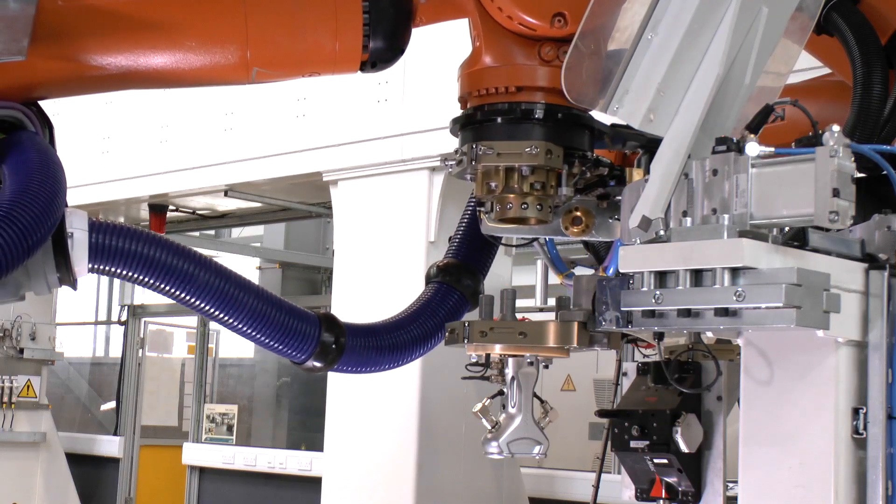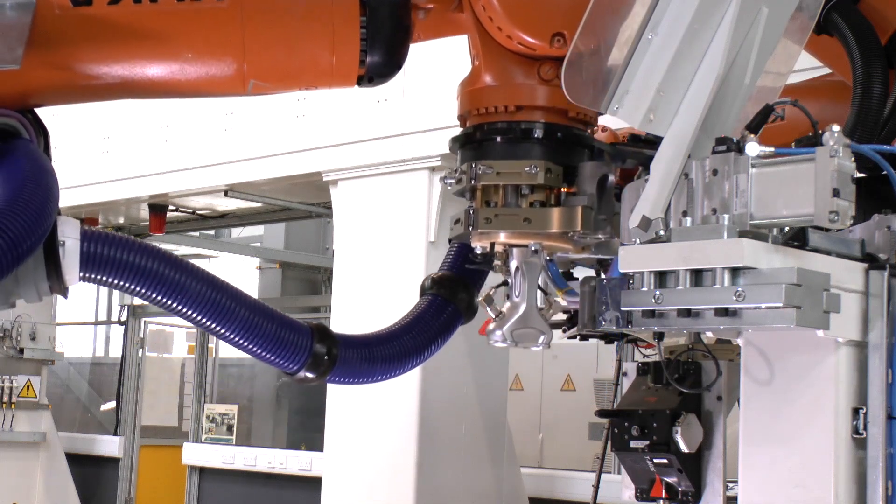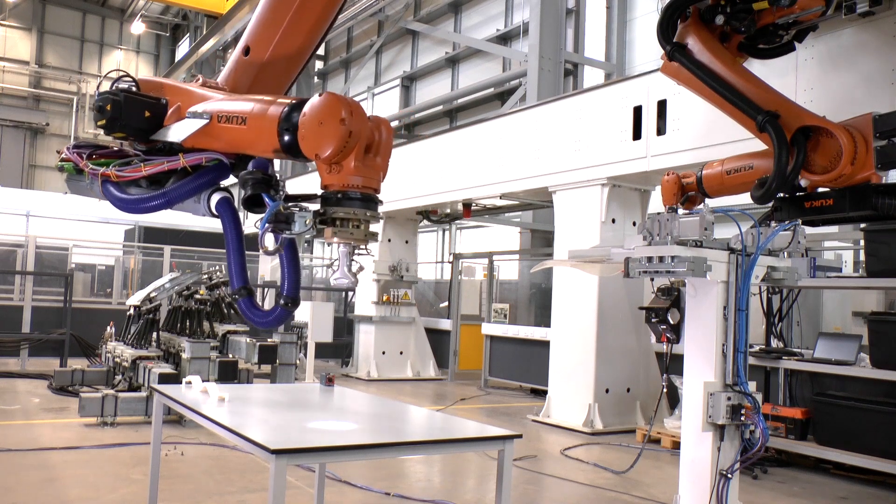Utilising this technology now, we can apply the force feedback system and our coupling contact feedback system to allow the robot to much more accurately guide the tool along the path necessary for scanning a component. This means that going forward we will be able to test much more complicated components, much more complex surfaces, and determine with a high degree of reliability what's wrong with the path.